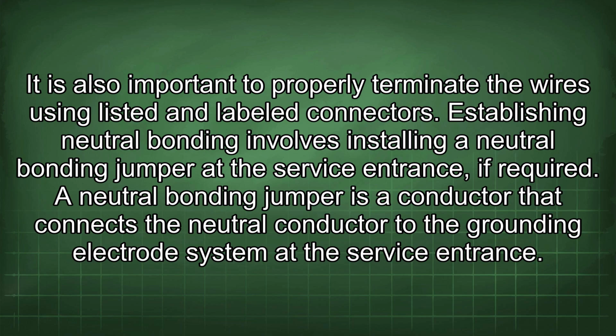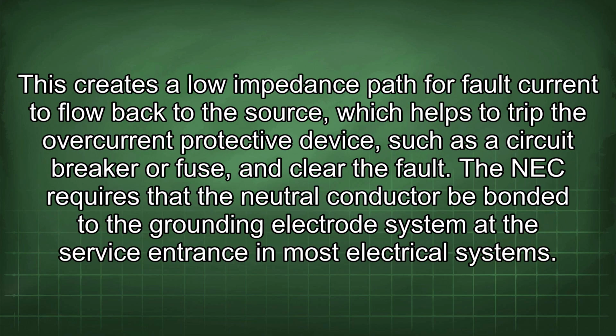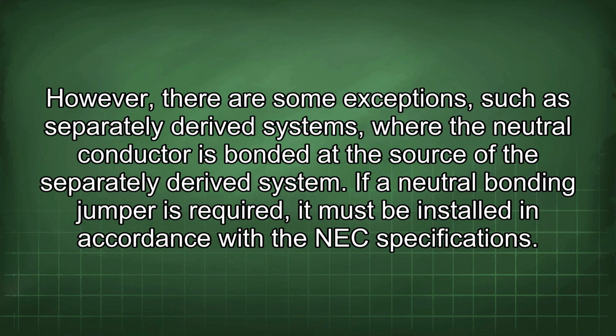A neutral bonding jumper is a conductor that connects the neutral conductor to the grounding electrode system at the service entrance. This creates a low impedance path for fault current to flow back to the source, which helps to trip the overcurrent protective device such as a circuit breaker or a fuse, and clear the fault. The NEC requires that the neutral conductor be bonded to the grounding electrode system at the service entrance in most electrical systems. However, there are some exceptions, such as separately derived systems, where the neutral conductor is bonded at the source of the separately derived system.